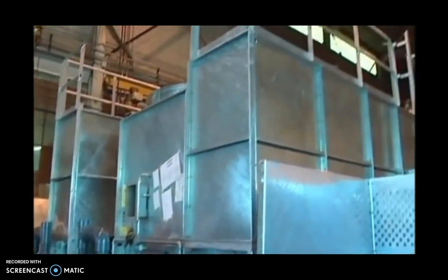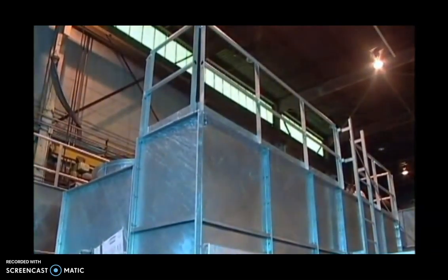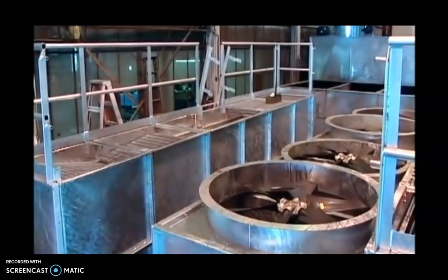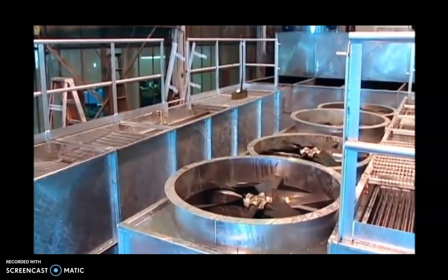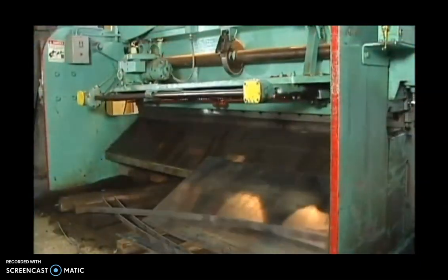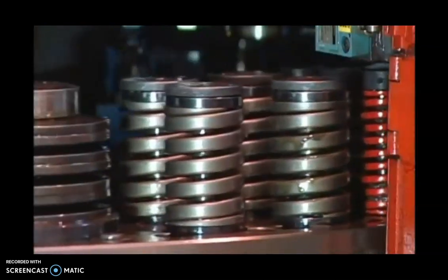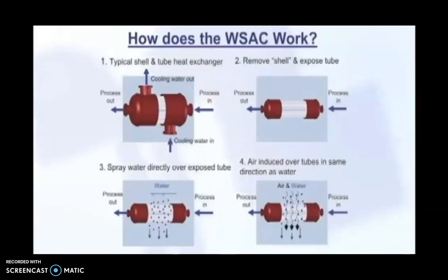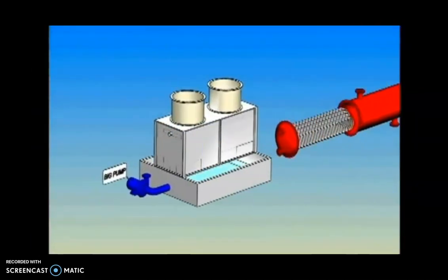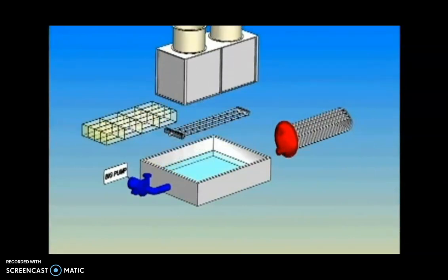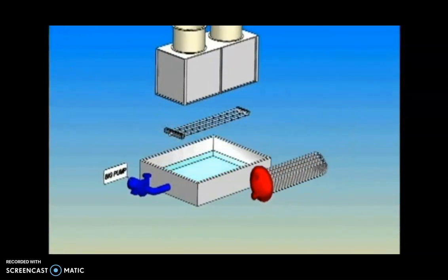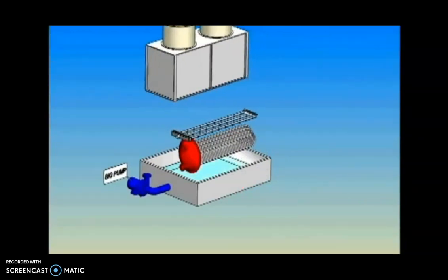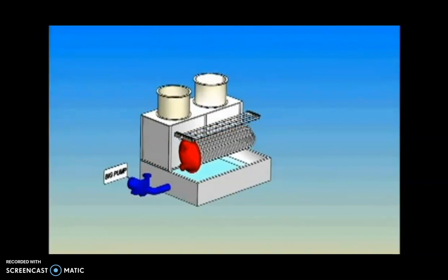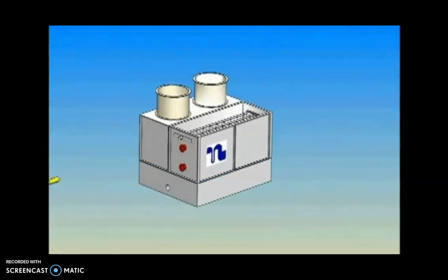The Niagara Wet Surface Air Cooler, or WSAC, is a heat removal device used to efficiently and reliably cool or condense various liquids or gases. One way of describing how a WSAC works is to compare it to a typical shell and tube heat exchanger. A shell and tube is a sensible cooling device where the process stream being cooled is on one side of the tubes, and the cooling water, normally from a cooling tower, is on the other side. If you remove the shell, expose the bare tubes, spray water and induce air over the tube surfaces, you now have an evaporative heat transfer device known as a wet surface air cooler.